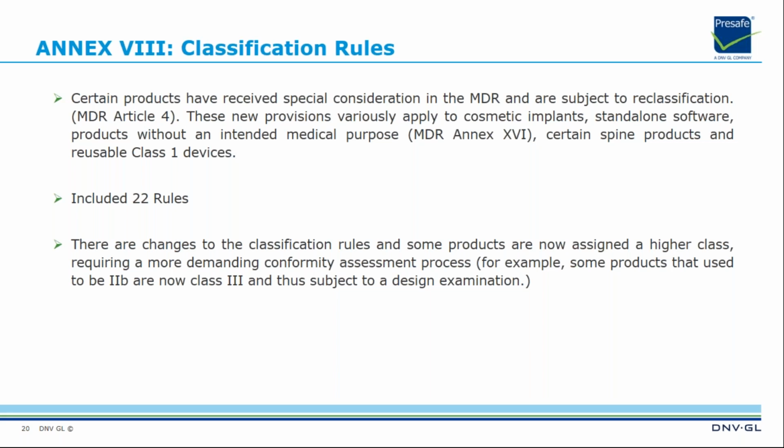These new provisions are usually applied to cosmetic implants, standalone software products without an intended medical purpose based on Annex 16, and certain spine products and reusable class 1 devices. It includes 22 rules, grouped in 4 classification groups: non-invasive devices, invasive devices, active medical devices, and special rules.